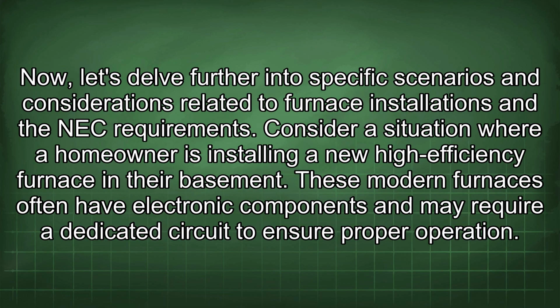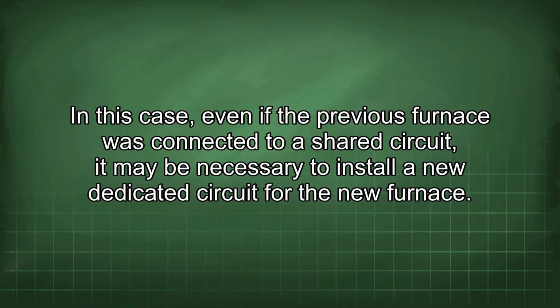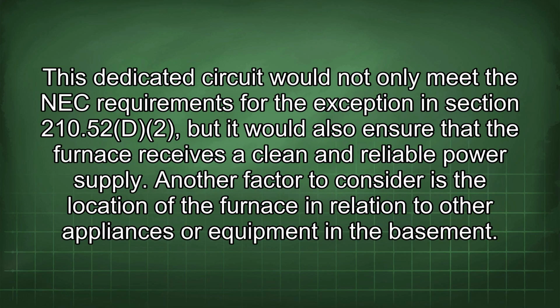Now, let's delve further into specific scenarios and considerations related to furnace installations and the NEC requirements. Consider a situation where a homeowner is installing a new high-efficiency furnace in their basement. These modern furnaces often have electronic components and may require a dedicated circuit to ensure proper operation. In this case, even if the previous furnace was connected to a shared circuit, it may be necessary to install a new dedicated circuit for the new furnace. This dedicated circuit would not only meet the NEC requirements for the exception in Section 210.52(D)(2), but it would also ensure that the furnace receives a clean and reliable power supply.